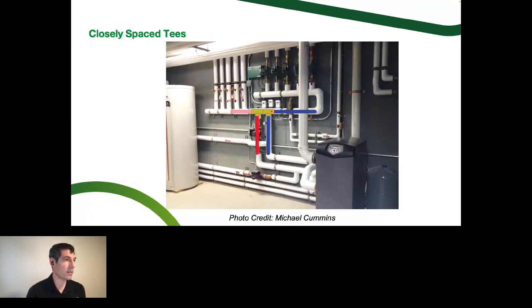And then additionally, we need a lot of real estate on the wall here to make this work if we're talking about 1.5-inch pipe or something like that. So closely spaced tees, when you pick them up at the wholesale house, are 2 tees that can fit in your hand. To do it right on the wall, you need to plan for that. That's going to take up a decent amount of space, and you might really have to think about how you can get that into a small mechanical room without breaking the rules and having a quick 90 off of that or something like that.